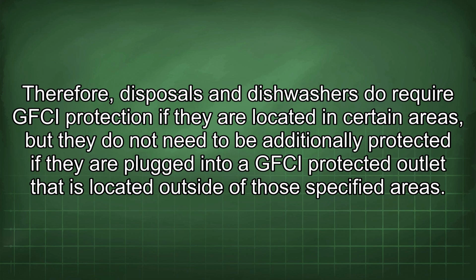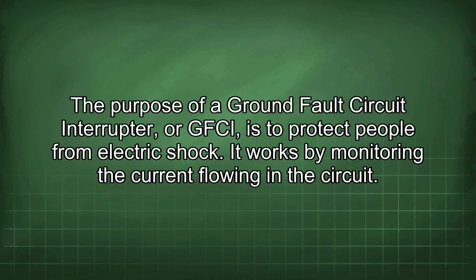Therefore, disposals and dishwashers do require GFCI protection if they are located in certain areas, but they do not need to be additionally protected if they are plugged into a GFCI protected outlet that is located outside of those specified areas. The purpose of a ground fault circuit interrupter, or GFCI, is to protect people from electric shock.